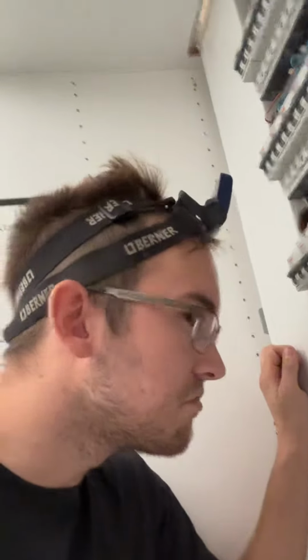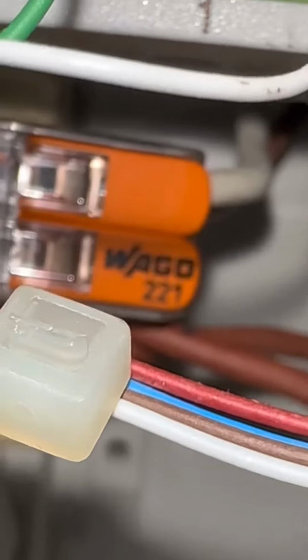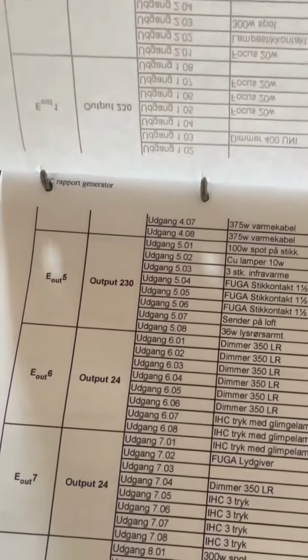So I removed all the cables and it didn't trip. Now it was narrowed down to only 8 cables, and when I removed this white cable, it didn't trip anymore. Then I just needed to find out what this white cable actually gave power to.